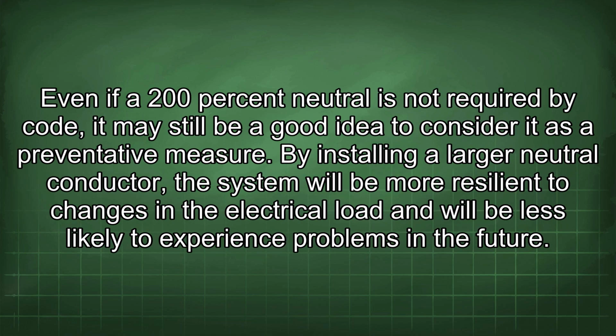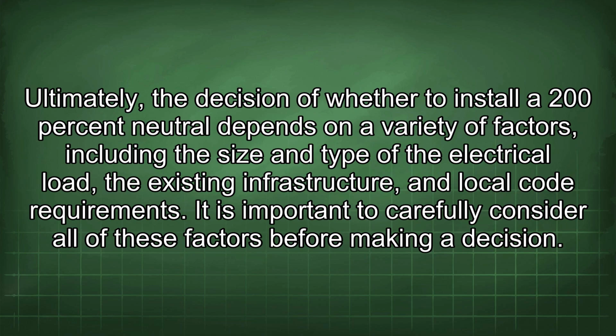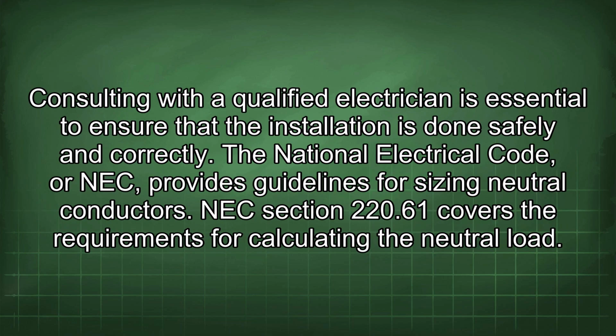Even if a 200% neutral is not required by code, it may still be a good idea to consider it as a preventative measure. By installing a larger neutral conductor, the system will be more resilient to changes in the electrical load and will be less likely to experience problems in the future. Ultimately, the decision of whether to install a 200% neutral depends on a variety of factors, including the size and type of the electrical load, the existing infrastructure, and local code requirements. It is important to carefully consider all of these factors before making a decision. Consulting with a qualified electrician is essential to ensure that the installation is done safely and correctly.